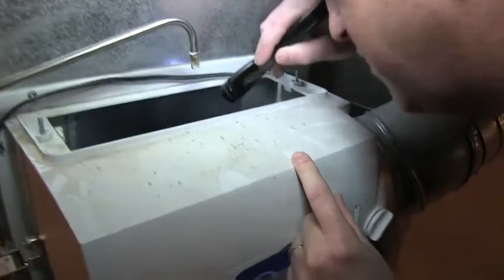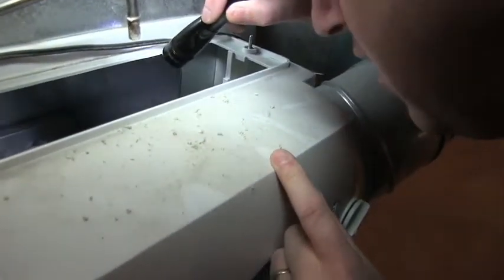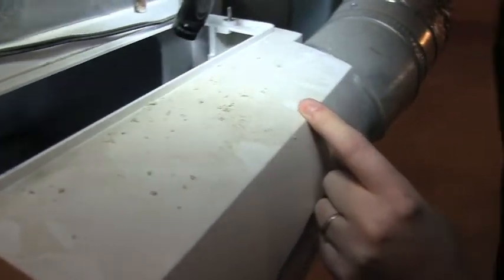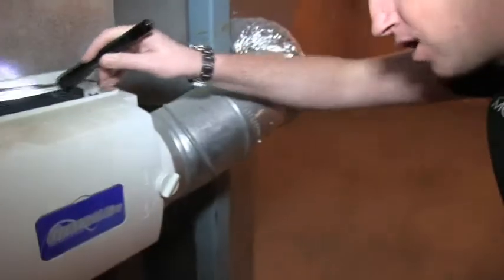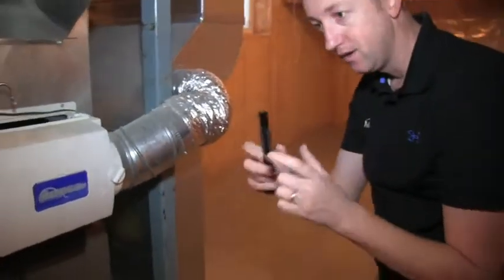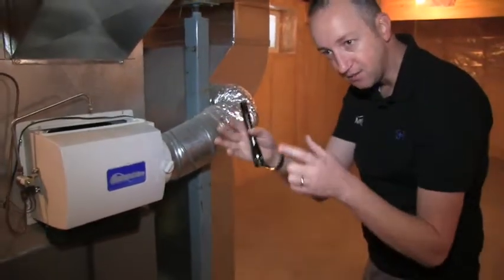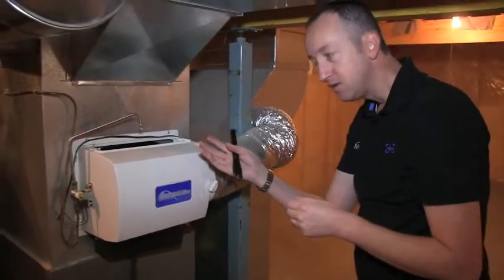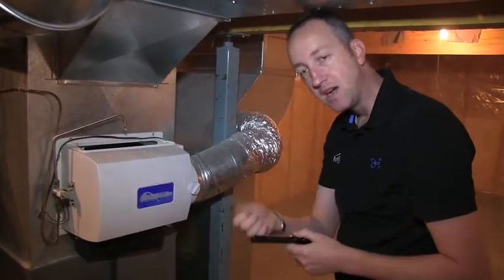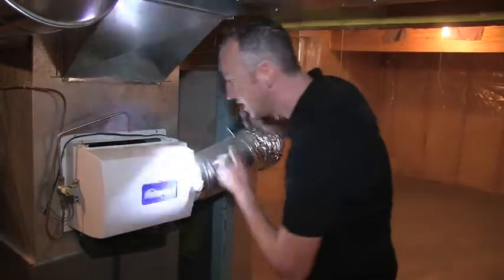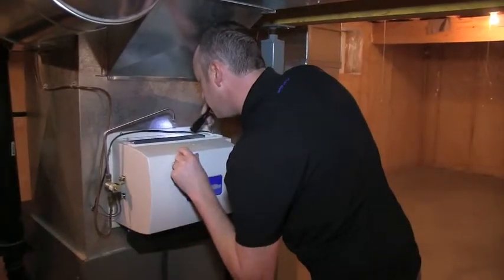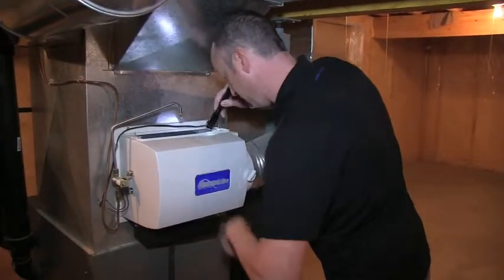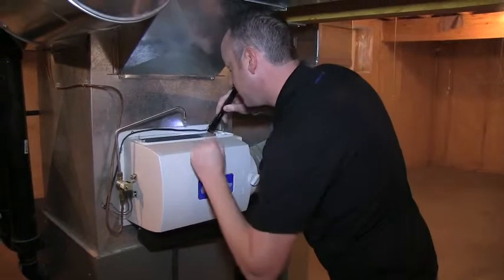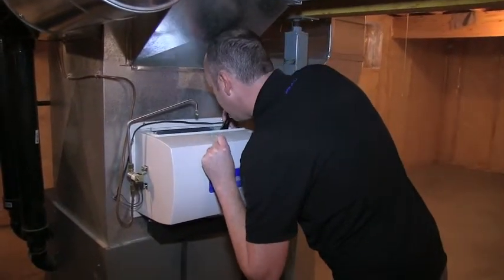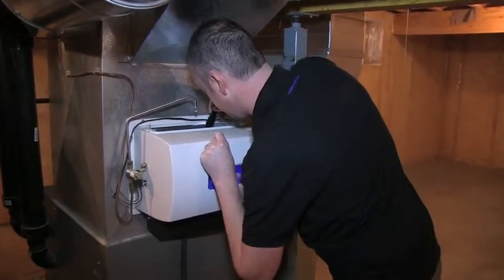The heat exchanger is the most important part of the furnace. It's what separates the off gases from the house air, and it's a big metal can with lots of fins on it. I want to get a look at those fins to make sure that there's no cracks or holes, rusted areas, etc. Especially rusted areas next to a humidifier with a dirty filter, which then is probably dumping water inside there. In this case, everything looks great.